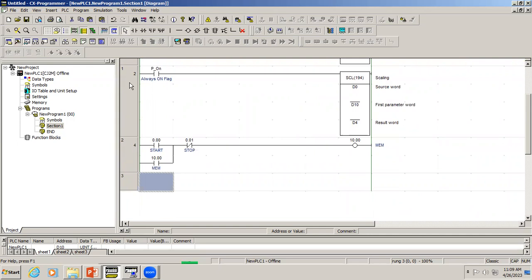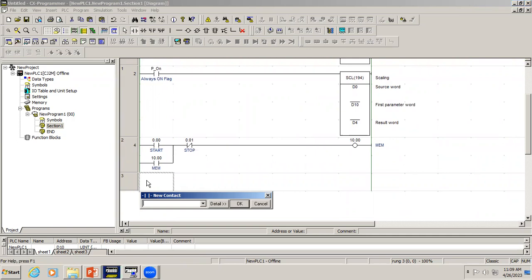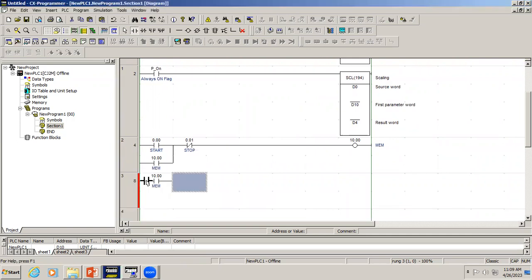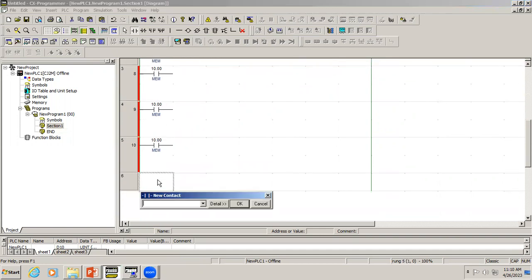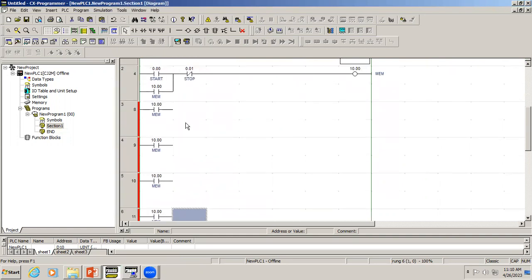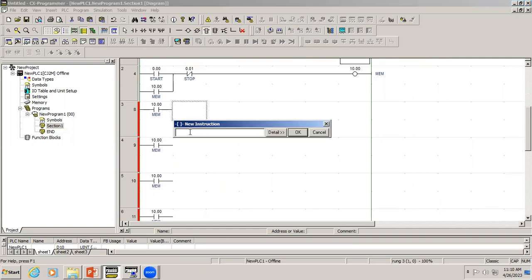Right now we have low level and high level, so I'm going to use a comparator. For the comparator we use the less-than-or-equal-to sign. I'm using address D4 for the analog input value that we get from the scale block, and the set point will be D20, which will be the low level value.